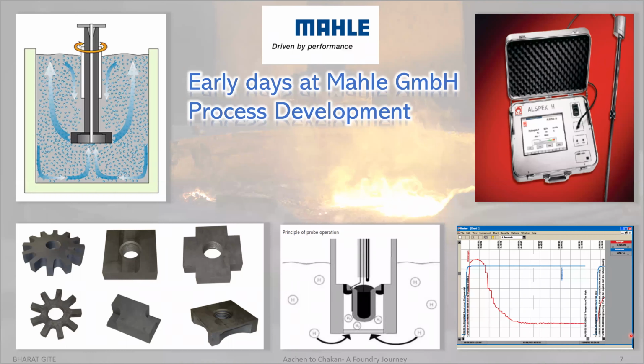It is built around an innovative electrochemical sensor that is capable of rapid and real-time measurement of hydrogen. Having a base of ceramic material, calcium stabilized zirconia, it has two different electrodes. One is called the reference electrode and the other is called the measuring electrode. We can see the schematic diagram here in this area where the probe is deep in the aluminum melt.